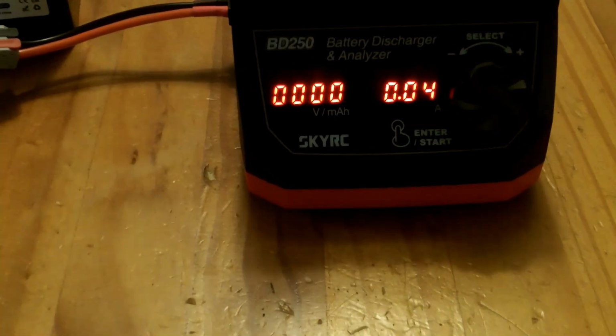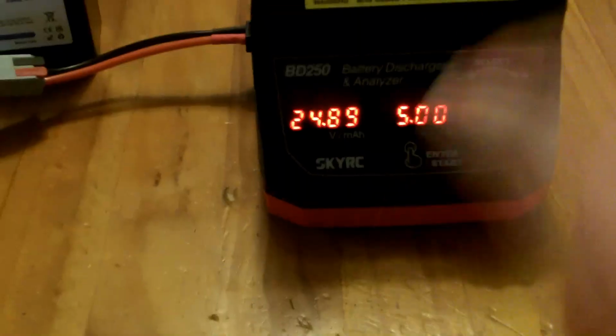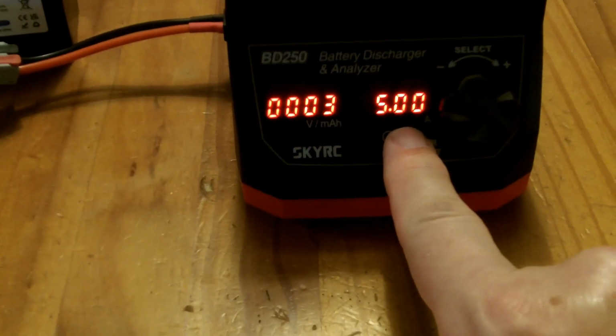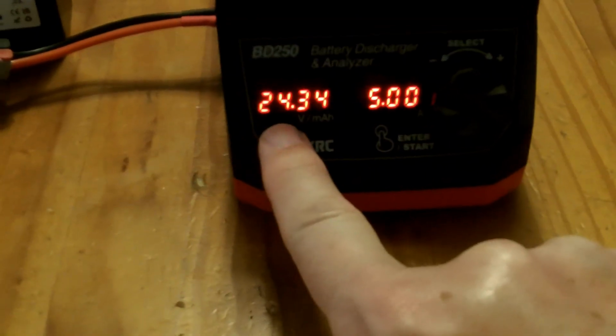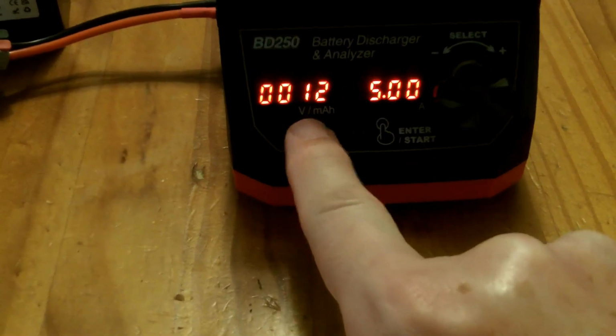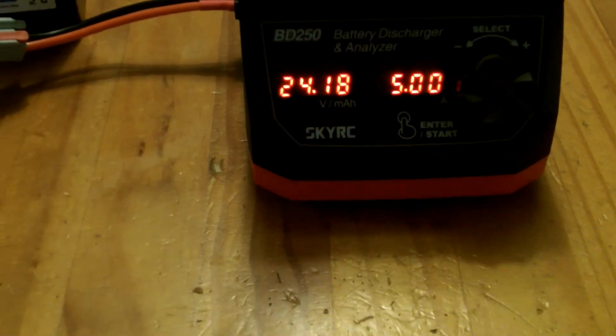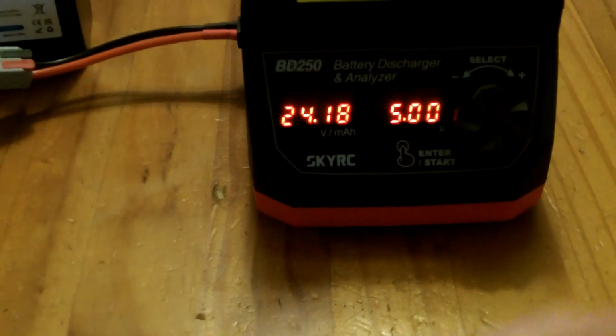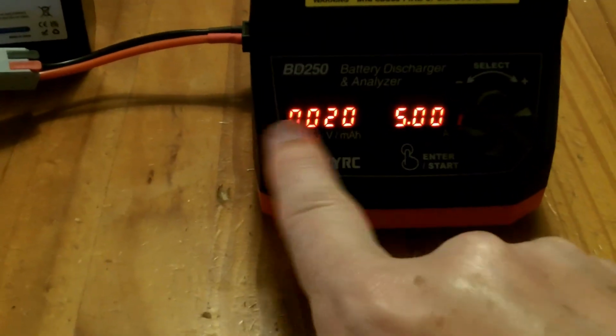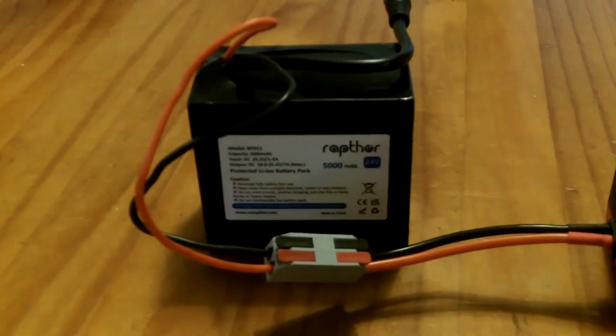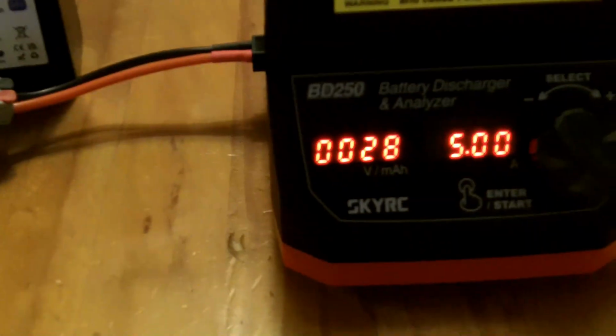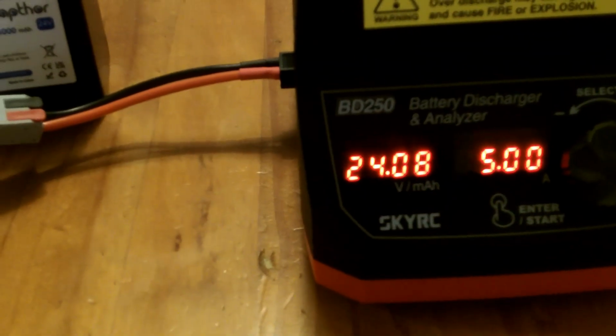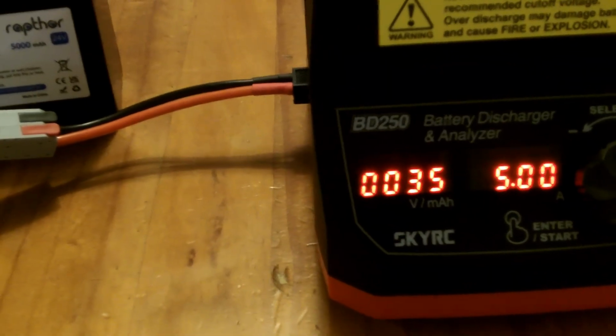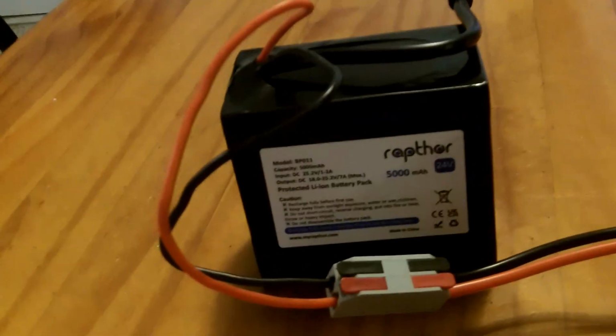Okay, so it is discharging and drawing 5 amps out of the battery. The current battery voltage is 24 volts, and it's delivered 12 milliamp hours so far. We're looking for this to get up to 5,000 or greater to meet that 5,000 milliamp hour capability. If it hits 4,500 to 4,800, that's pretty good all in all. If it goes above 5,000, great.